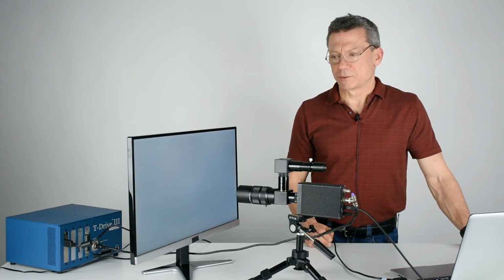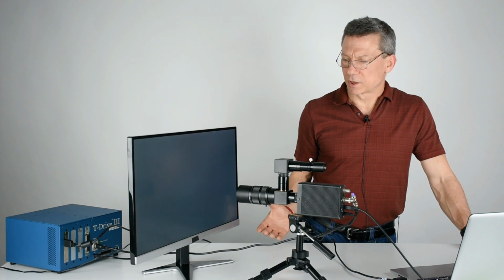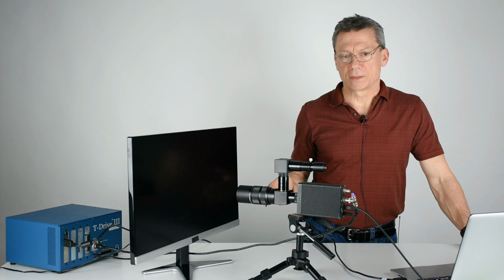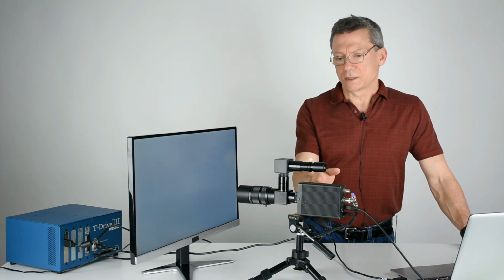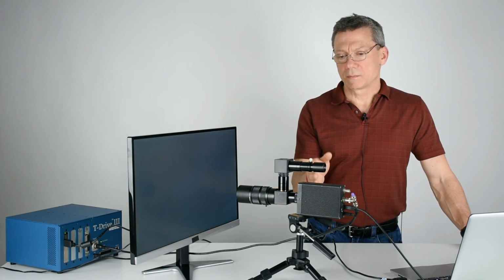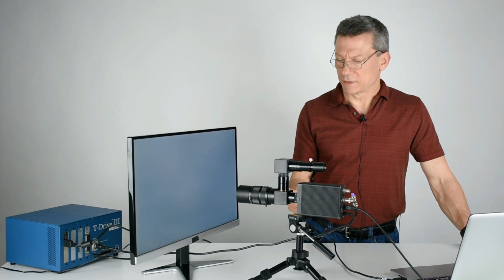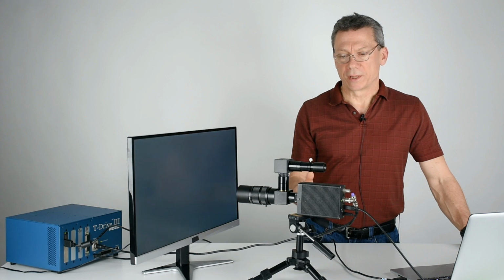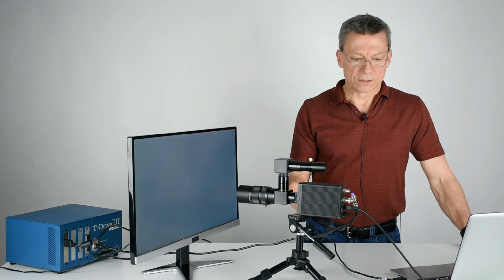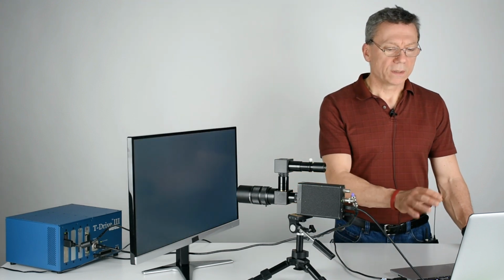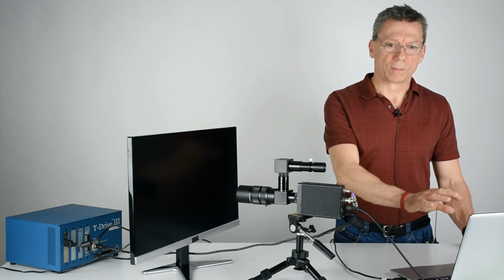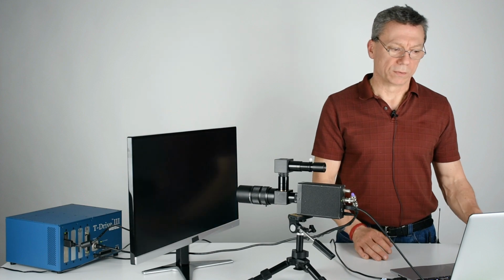And we'll do a series of measurements. So what's happening here is the software is commanding the T-Drive to put up blink patterns on the display under test. The TRD is measuring the luminance rise and fall time of these blinking patterns. And these are not just black and white, but also gray to gray that we're measuring. Each of these is being recorded, and then the data is being logged in graphical and tabular form in the GLRT software, which we'll go into more detail in a second.